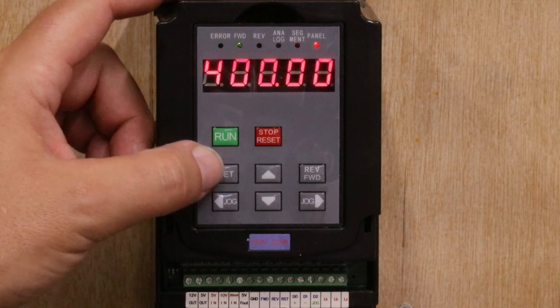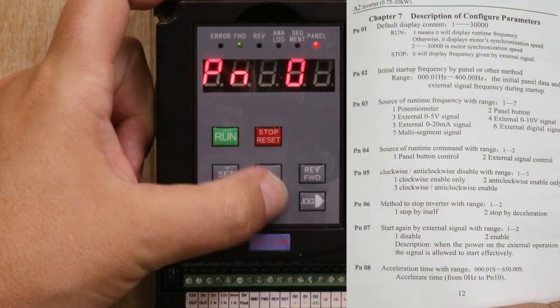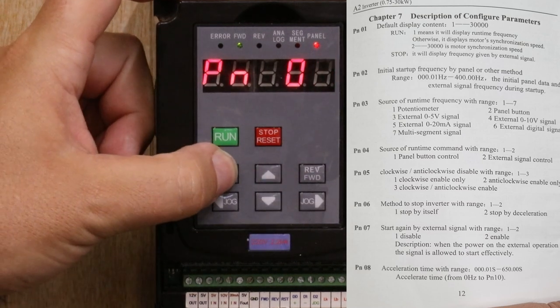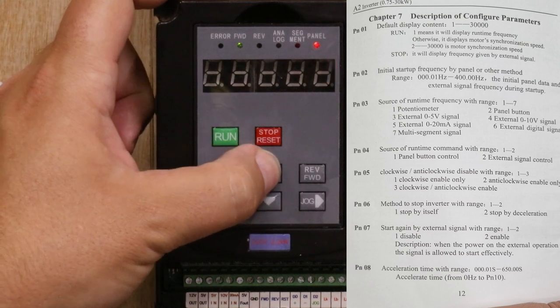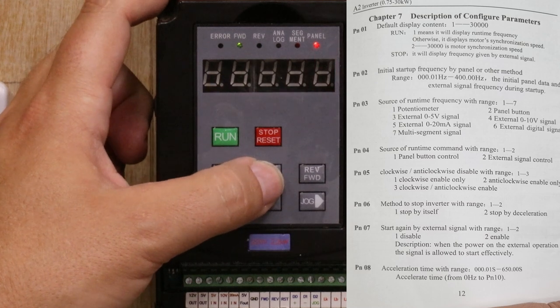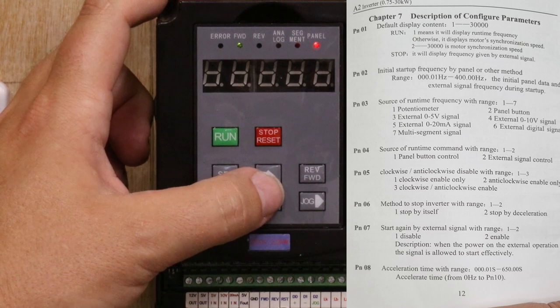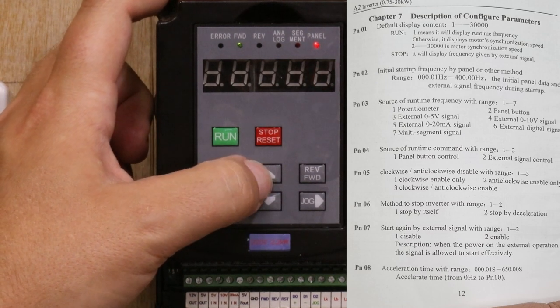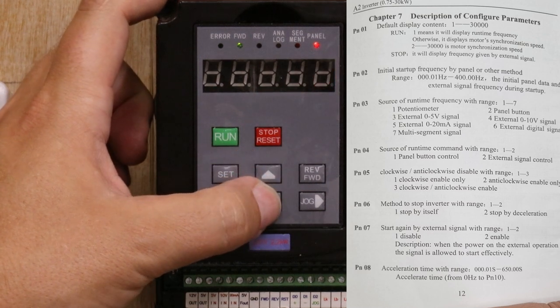So the first thing we're going to do is go into the menu system and we're going to go to Pn03 and click set. Now there are a couple of different options in this. Number two is telling it to pick the signal up from the panel. Number three is telling it to pick the signal up from five volt. Number four is 10 volt, and there are a couple of other options as well after this.